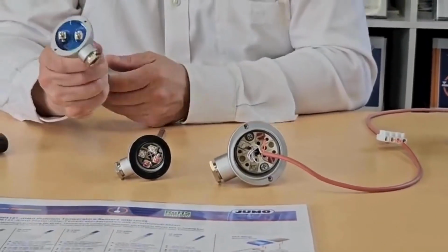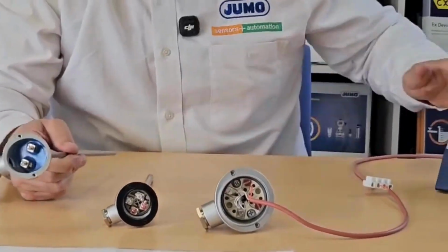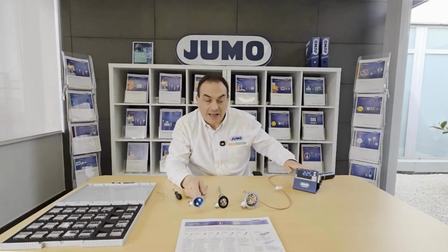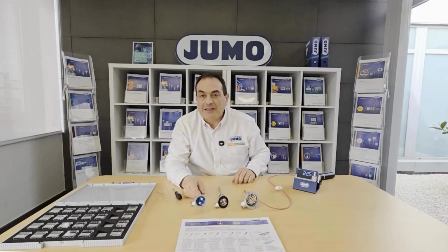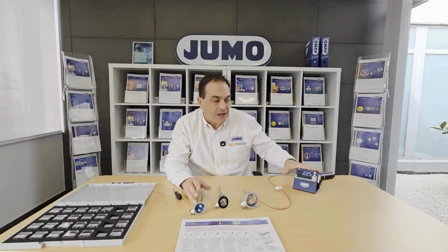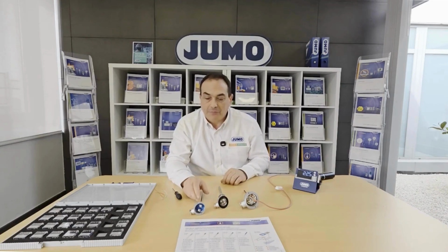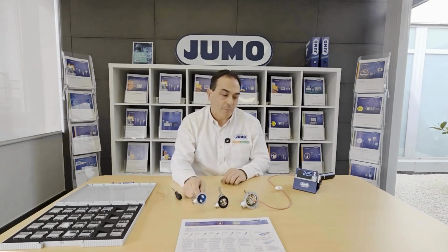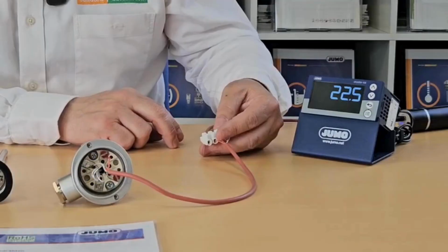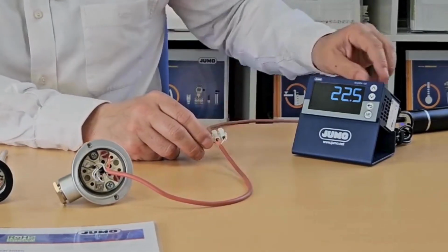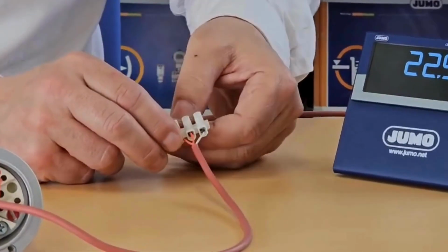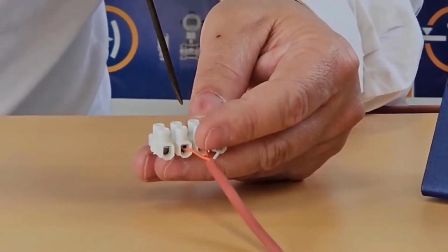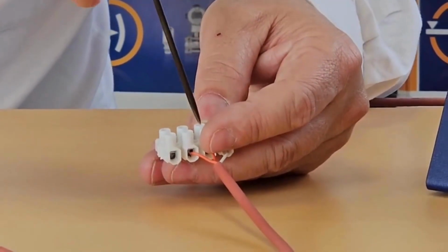If we had a 2 kilo ohm resistor, we could connect it to the electronic device, but internally you need to subtract, not add an offset, so the measurement is accurate, but also so you don't have to be constantly adjusting that parameter. I can use a 2-wire probe and connect it as if it were actually a 3-wire one. All I have to do is, from the cable in the installation that has 3 wires, join 2 of them together and we'll see what measurement difference there might be.